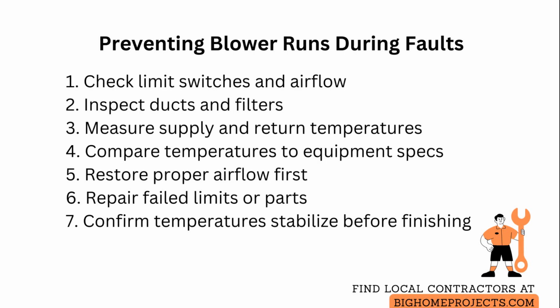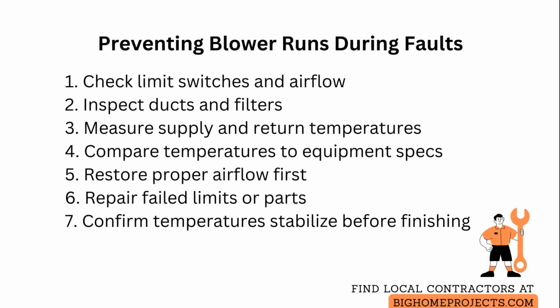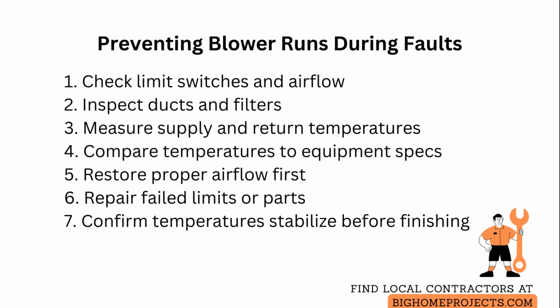If a high limit or secondary limit opens, the board will assume restricted airflow or a stuck burner condition and energize the blower even though ignition is disabled.